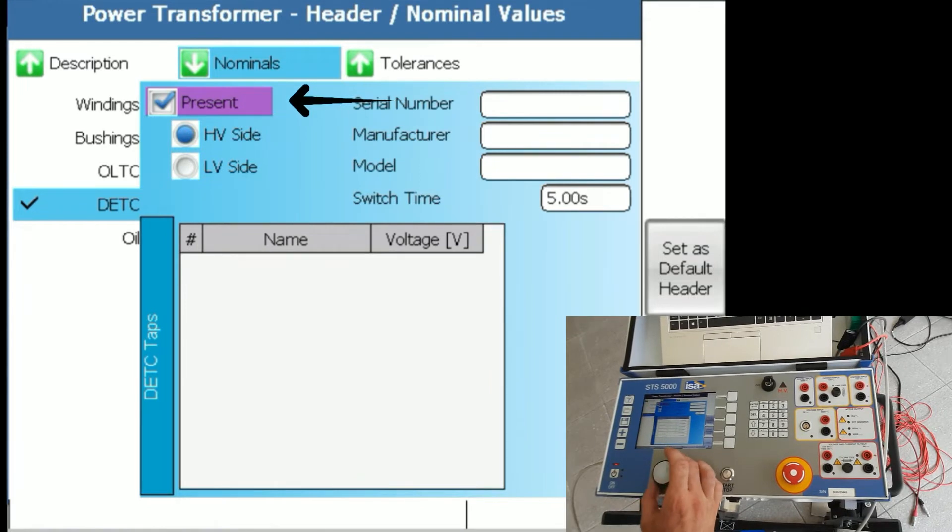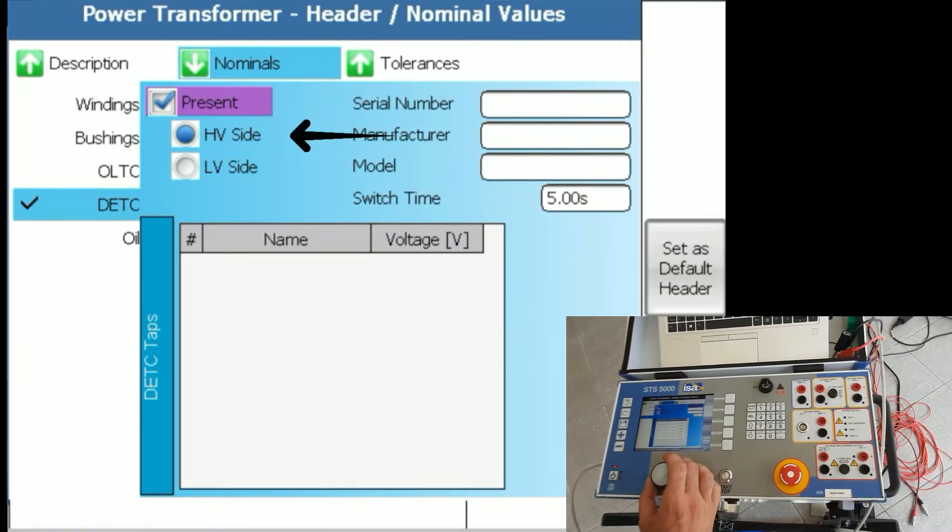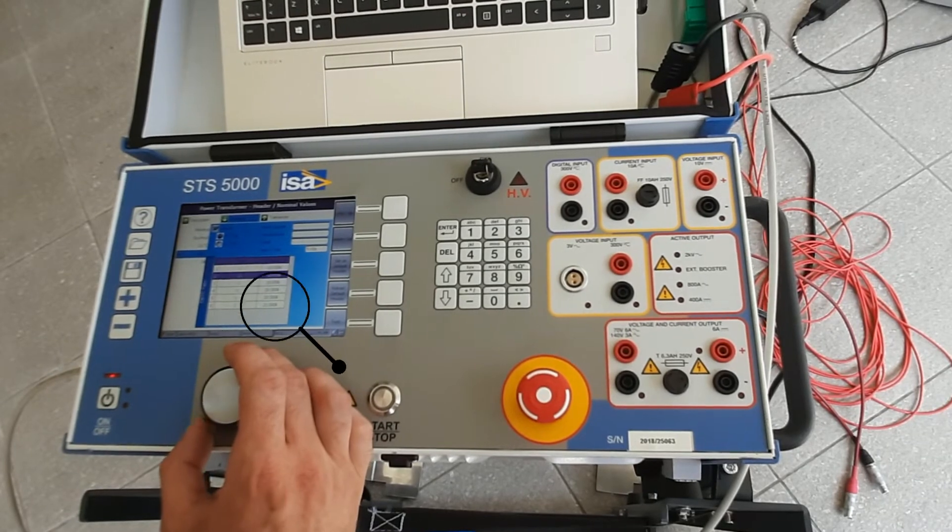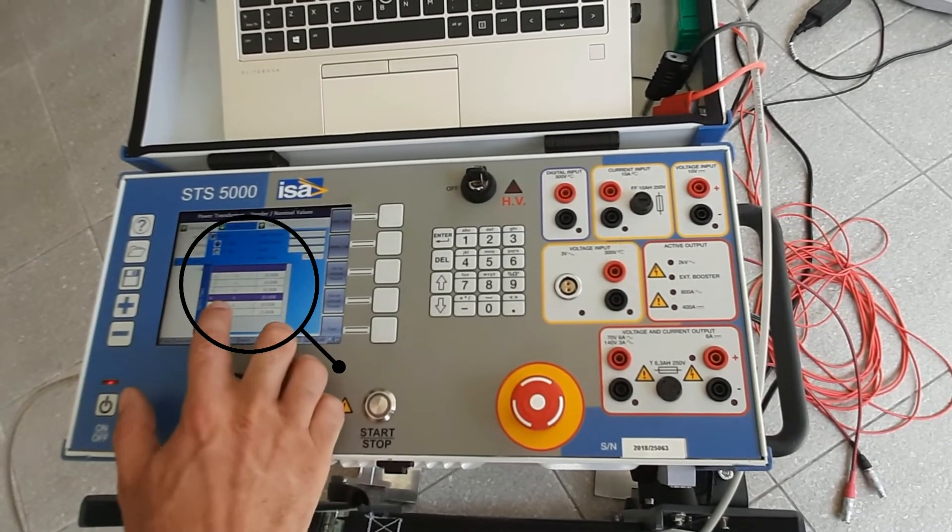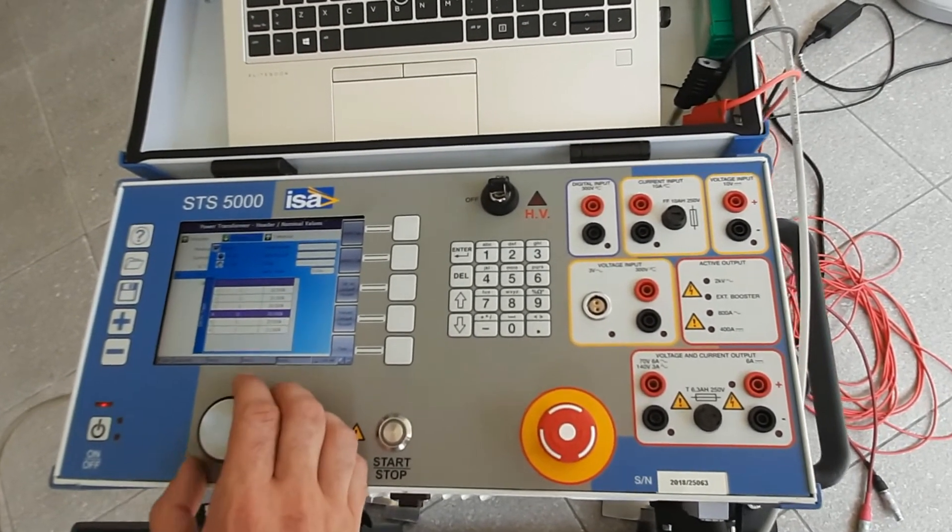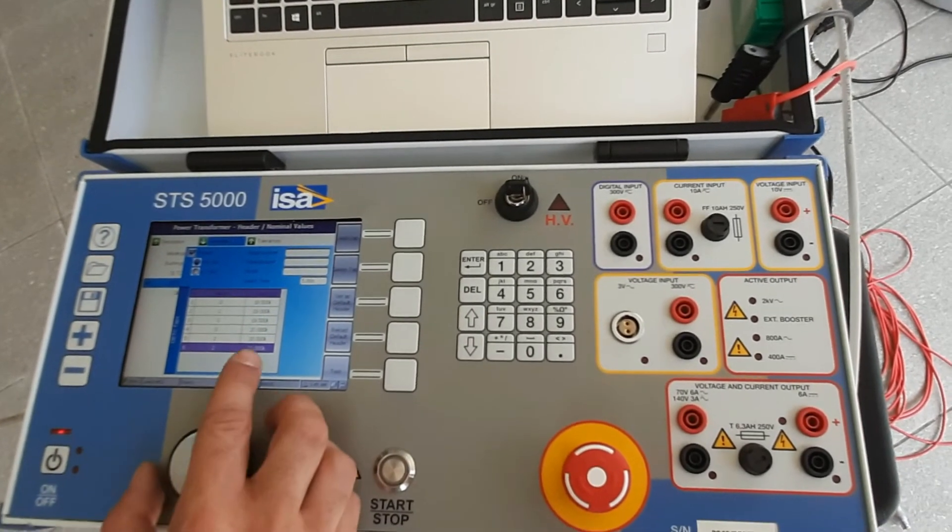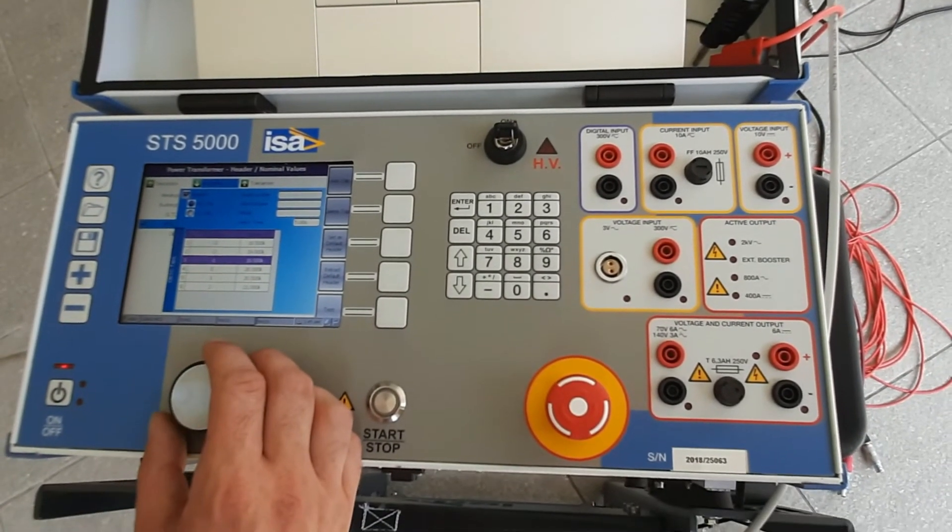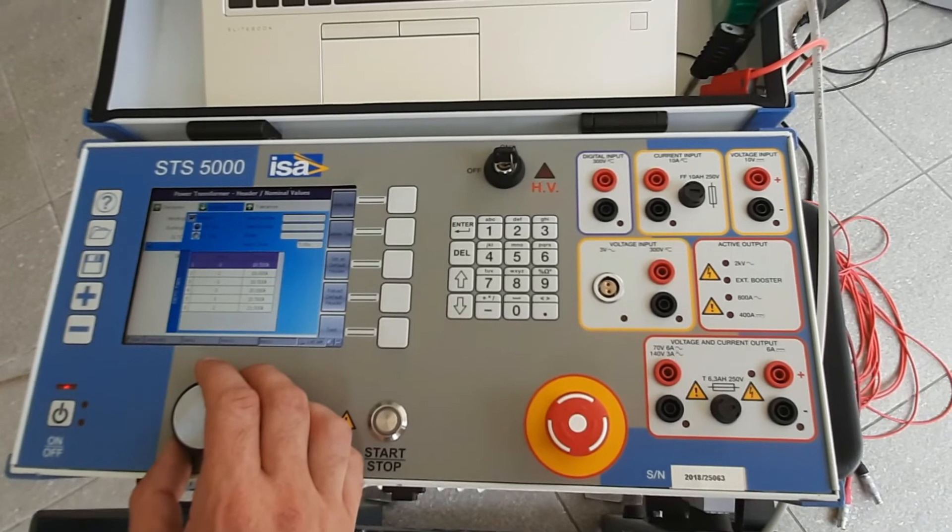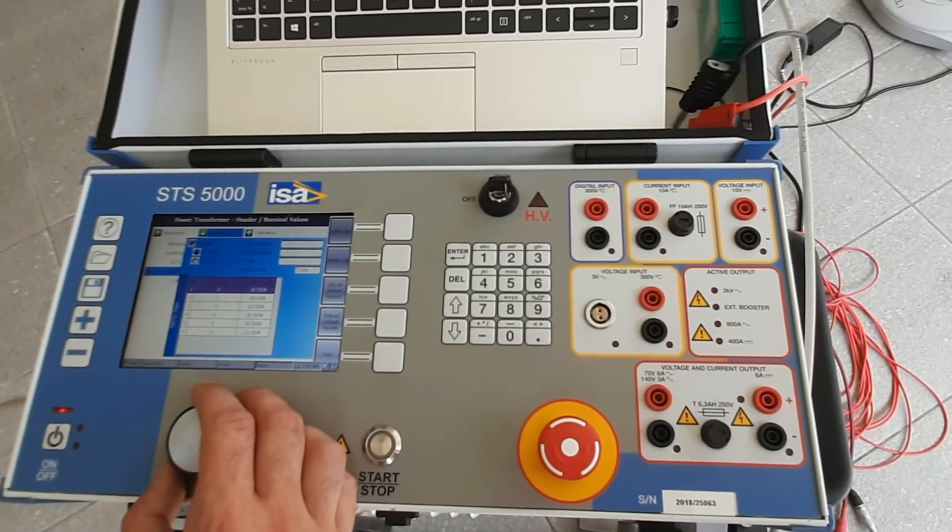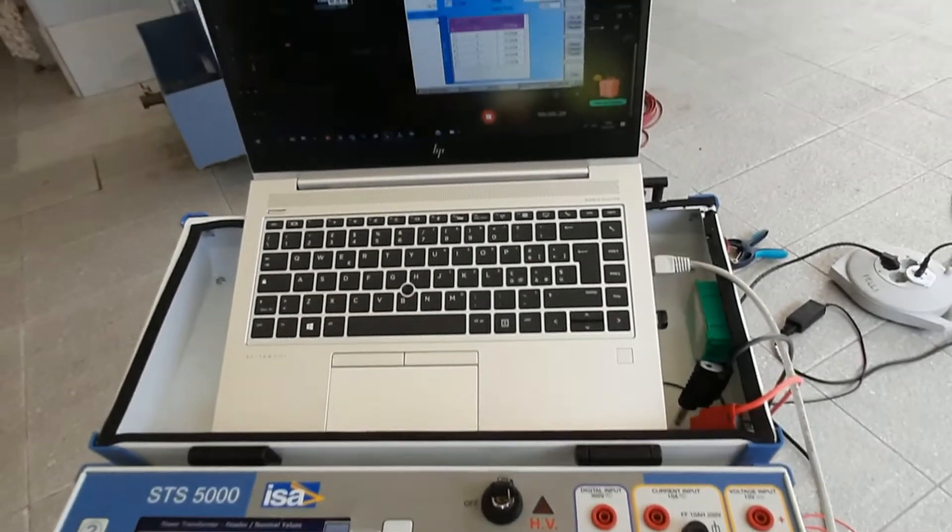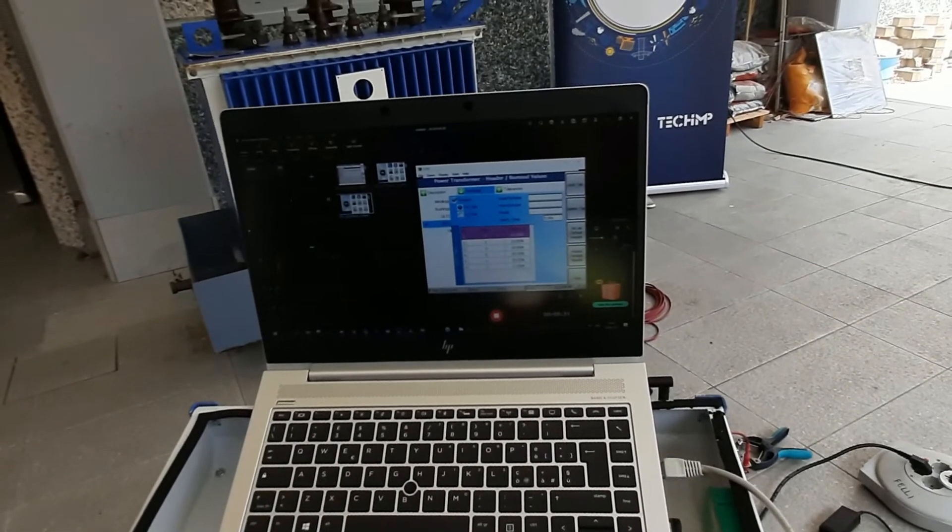So in our case, we have a de-energized tap changer and we said that this one is present. It is on the high voltage side and here we've already written what are the steps. So position zero is 20kV as we said. We have also positions one and two up to 21kV and positions from minus one to minus three.